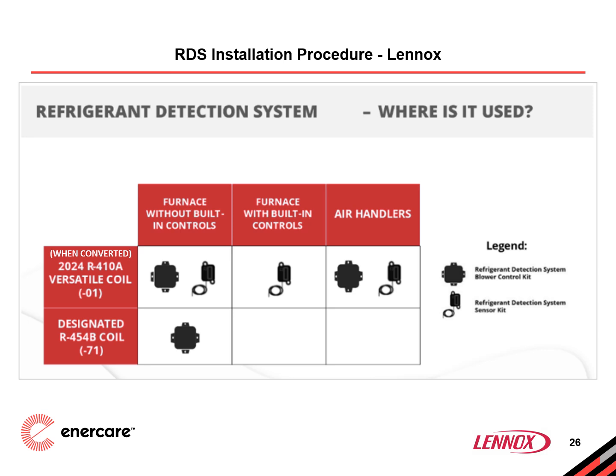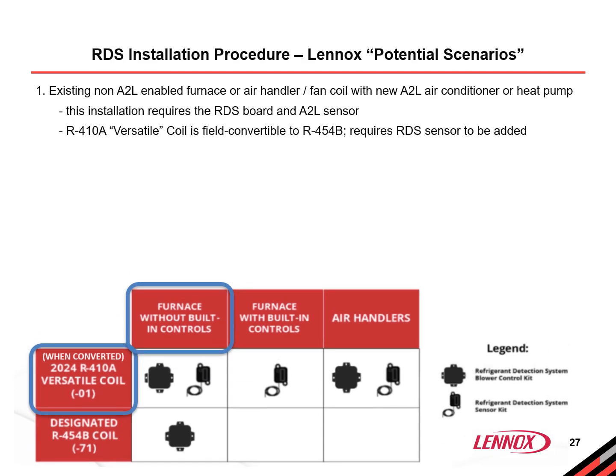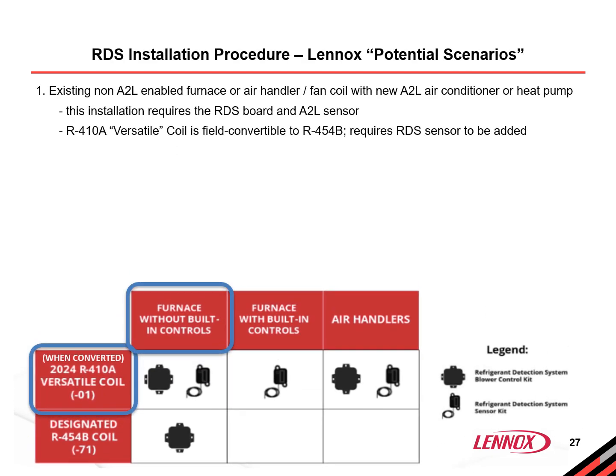Augmenting A2L refrigerants and the associated RDS components into new and existing HVAC systems will come in a few different ways, as can be seen by the infographic chart on the screen. Let's go through each of the possible configurations that you may be implementing out in the field. These configurations are designed to ensure compatibility and safety while upgrading or maintaining systems. We'll clarify what components are needed for proper setup in each scenario.